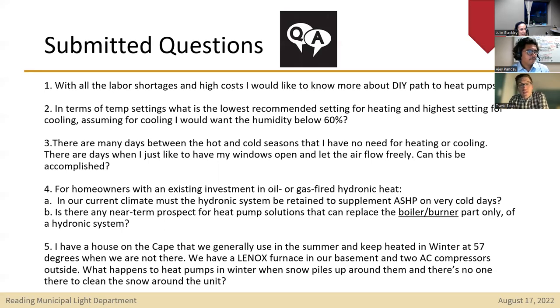Consistent with that, there's a question about cooling load. I mentioned that because in New England our systems are sized based on heating loads. Most contractors will do what's called a manual J, a load calculation for the home. We highly recommend it because that helps ensure you're getting a system that can effectively meet your needs. But so long as your system is sized for heating, you should have no issues with cooling.